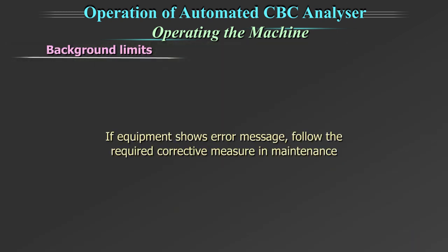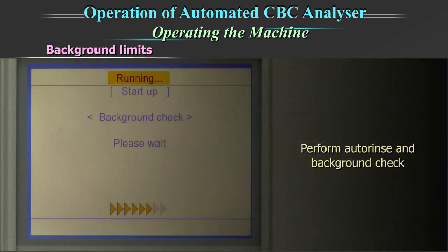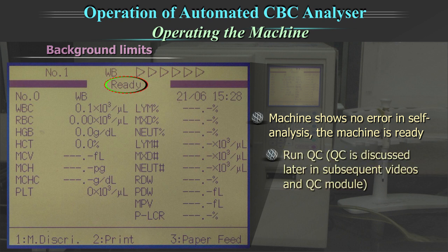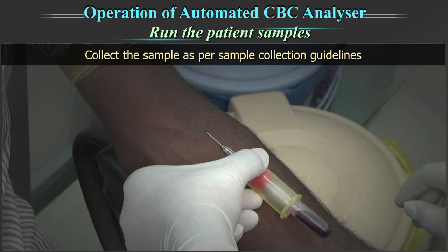In case the equipment shows an error message, follow the required corrective measures in maintenance and perform autorinse and background check. If the machine shows no error in self-analysis, it is ready for analysis. Run the quality control (QC) first. After quality control, run the patient sample.